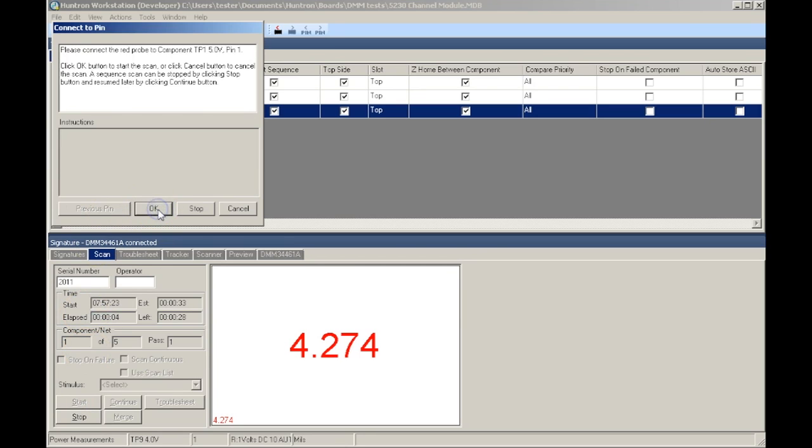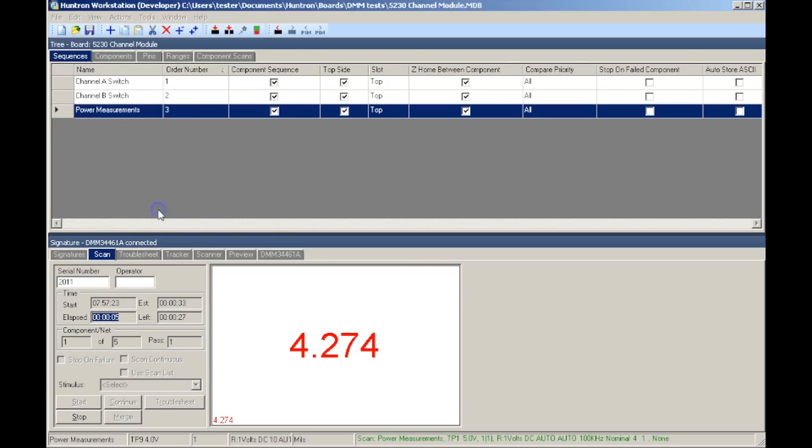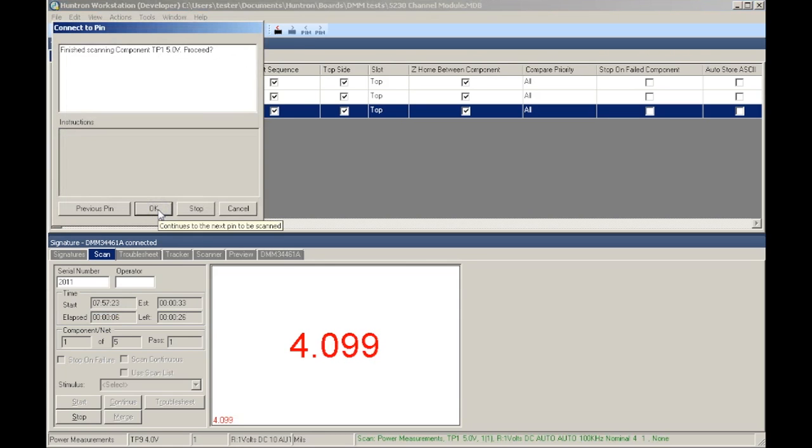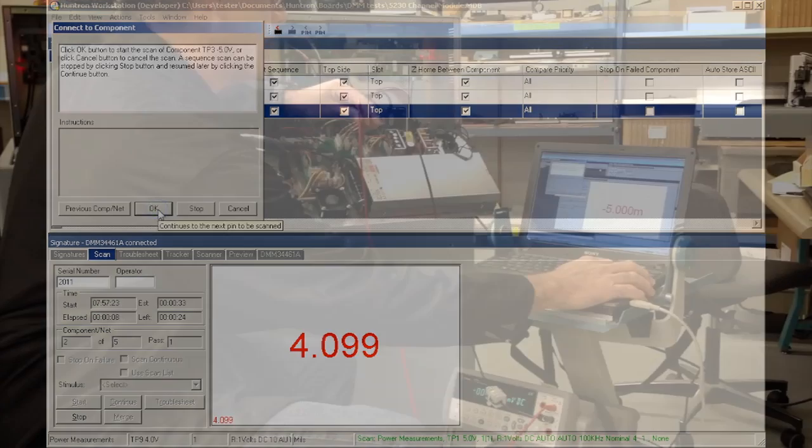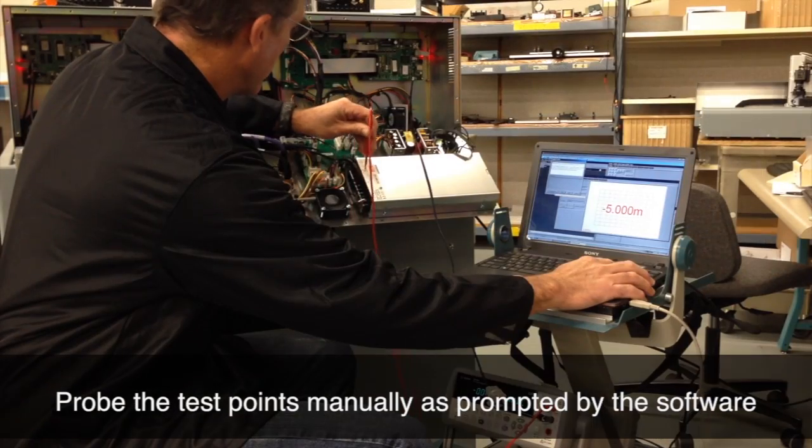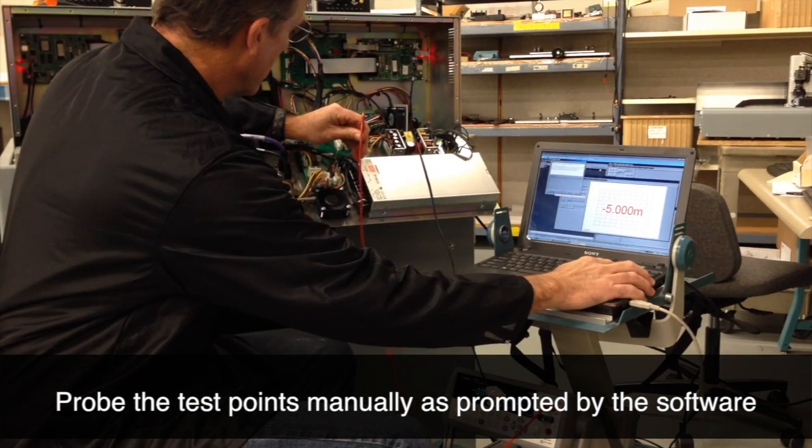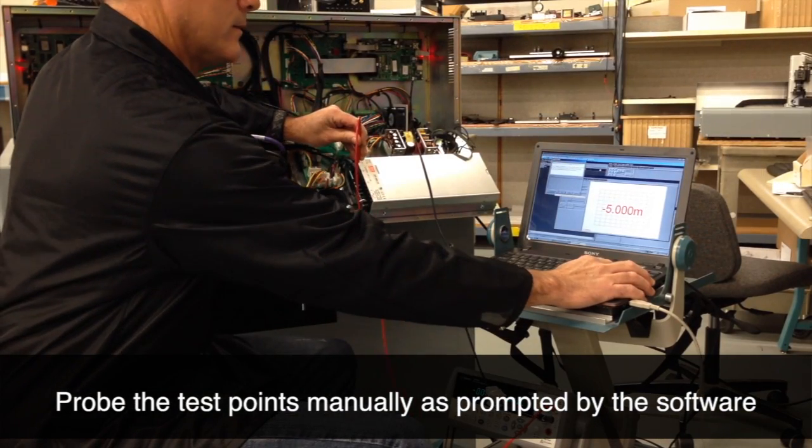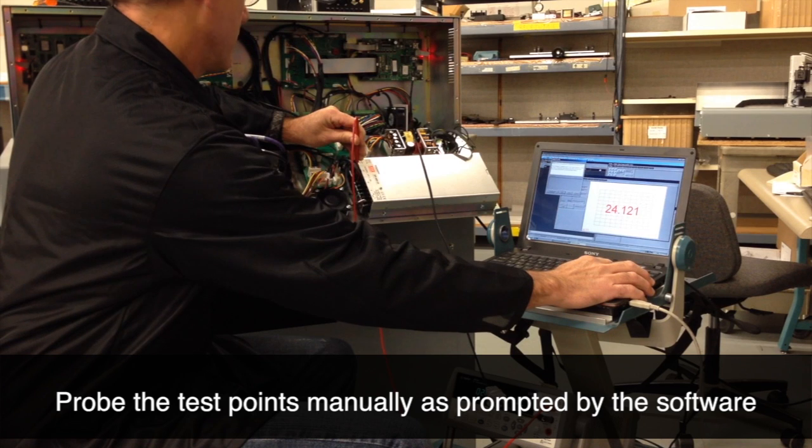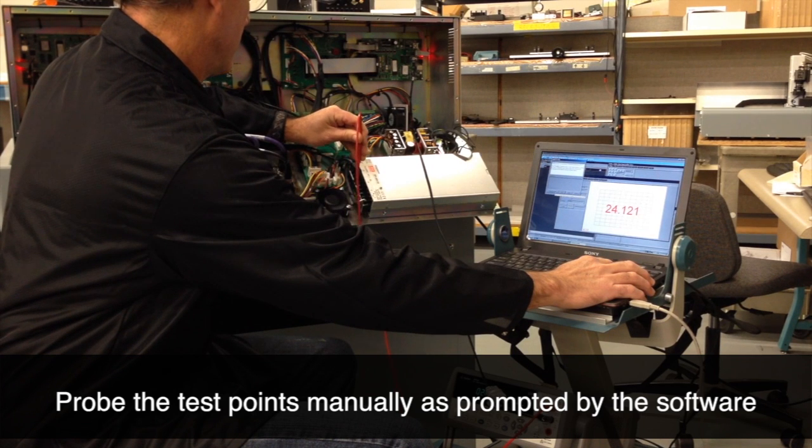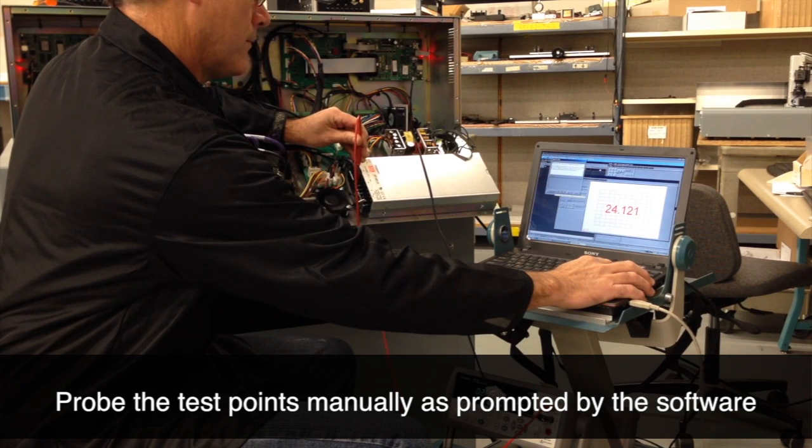Interfacing to the test points can be accomplished in two ways. Handheld probes can be used, and as the test progresses, the software will prompt you to test each point.